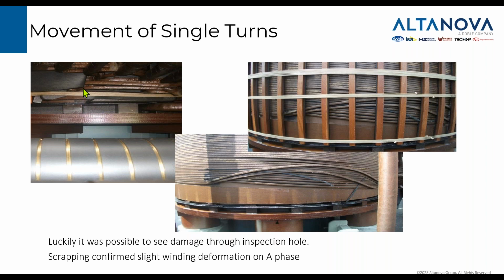So the customer decided to scrap this transformer, and we participated in the forensic investigation. During the forensic investigation, we saw some tap leads deformed in this transformer. That bracket was further away here, so the leads actually broke that bracket, and this was the condition of the transformer. So it wouldn't be identifiable by any other test than this SFRA test that we did, and even that was not straightforward to interpret. But fortunately, we got to the bottom of this.